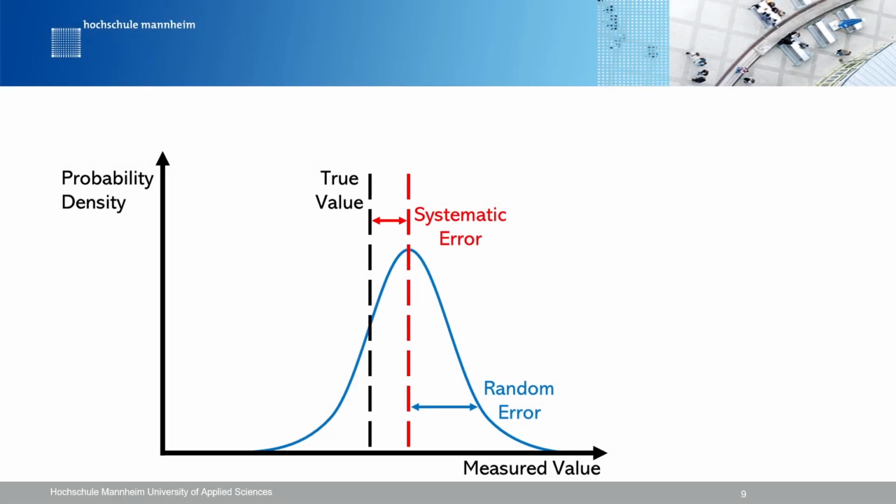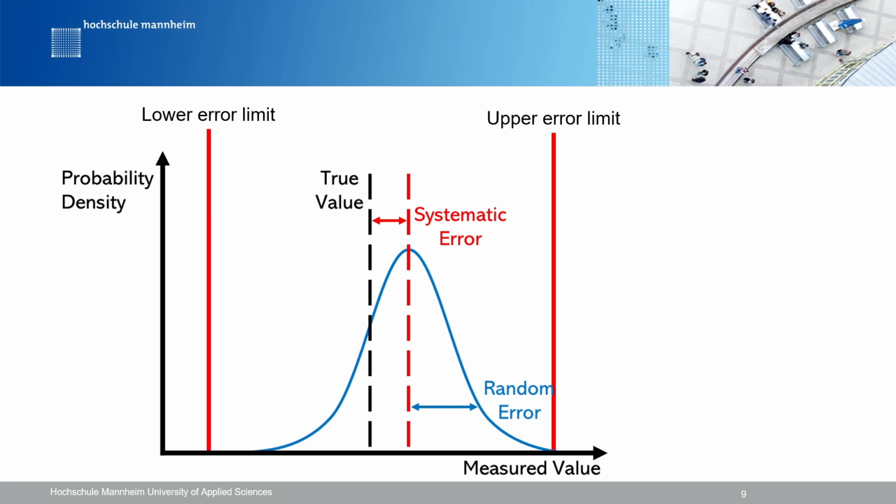In this context, the term officially calibrated signifies that the accuracy of the measuring device has undergone verification and certification by an independent official authority. It is important to clarify that many assume calibrated instruments always provide the true value without deviation, but this is not accurate. A calibrated device is not necessarily exceptionally precise. Rather, it is a device whose measurement accuracy has been assessed and certified by an independent official body.